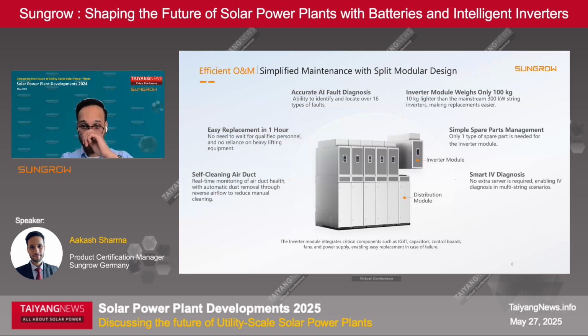But the second generation has a split modular design. The whole segment is split into an inverter module and a distribution module. The distribution module consists of cables and connections, while the inverter module consists of the core components, which are IGBTs, capacitors, fans - components relatively more prone to maintenance compared to others. This leads to easier replacement of these components.